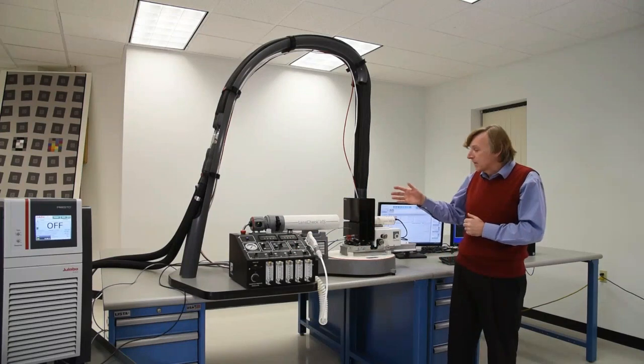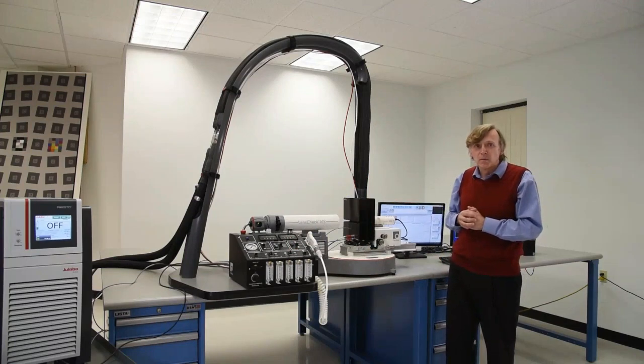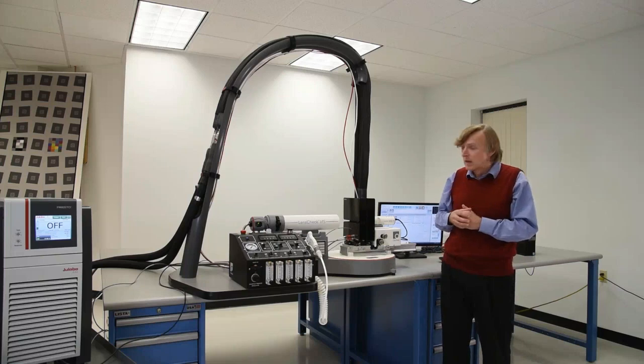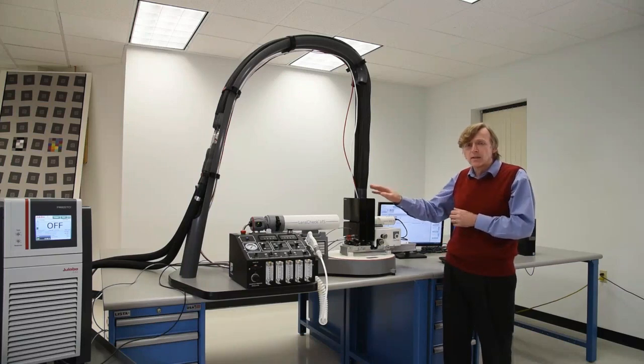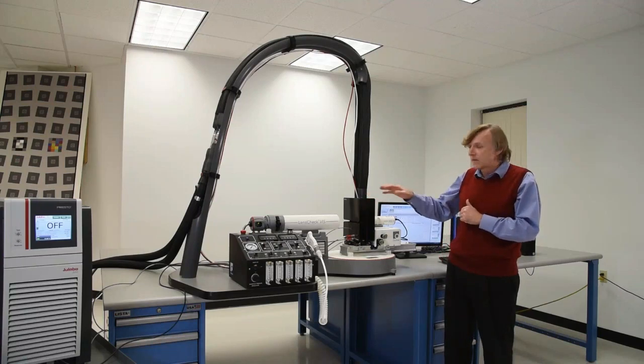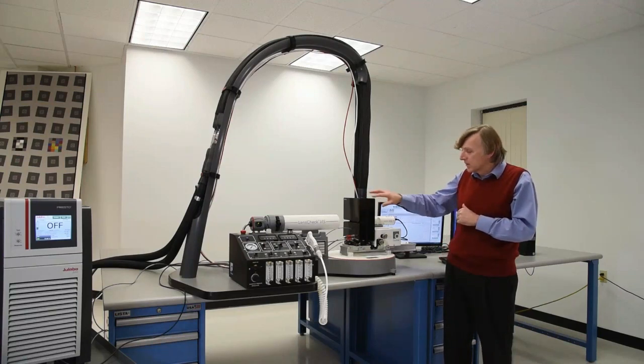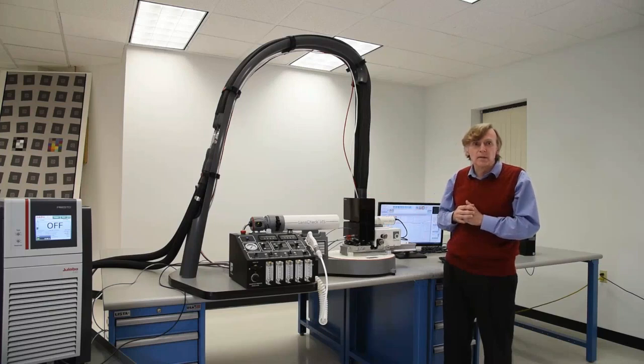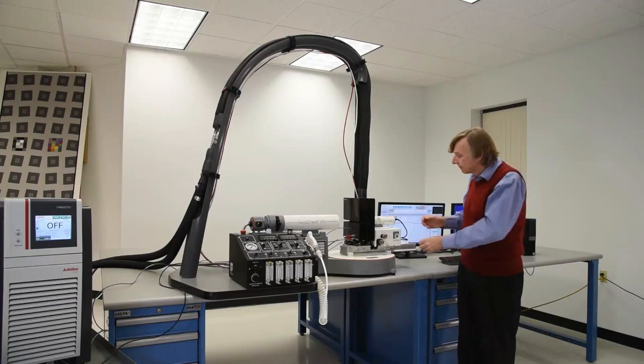And so we finally arrive at the thermal chamber itself. By its very nature, it does of course require thermal insulation. For ease of access to the interior of the chamber, this insulation is held in place magnetically and is readily removed. In the case of the TC1010, there are 3 pieces of insulation that we will now take off and put to one side.